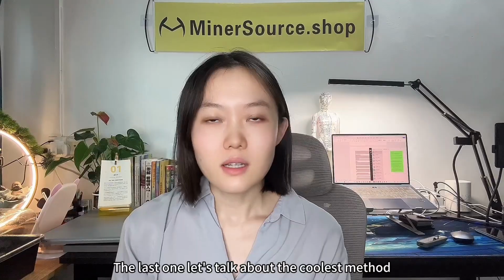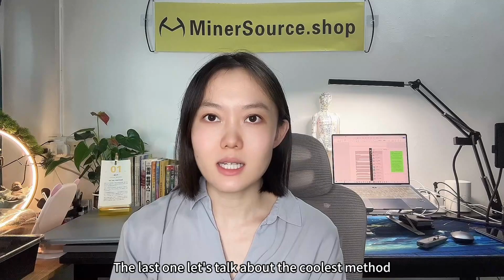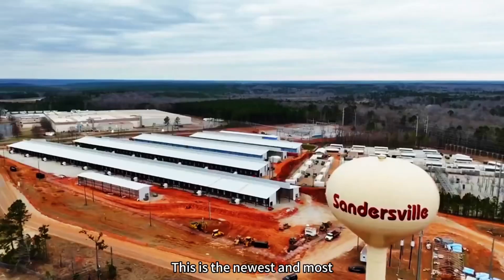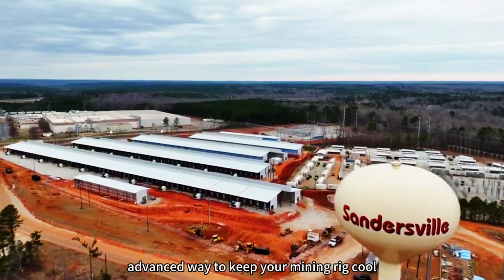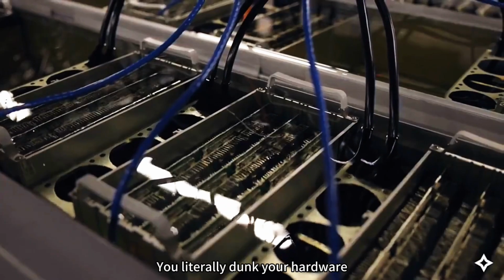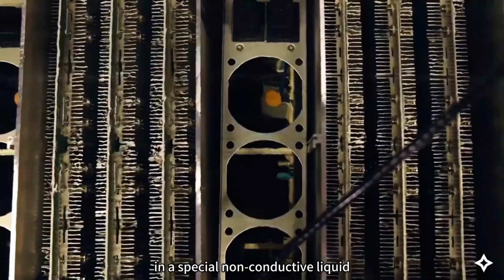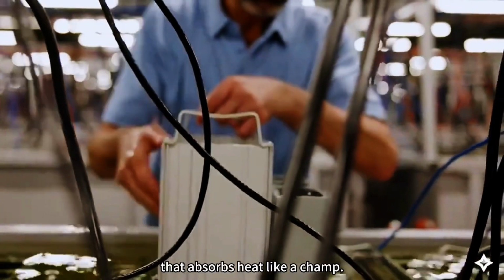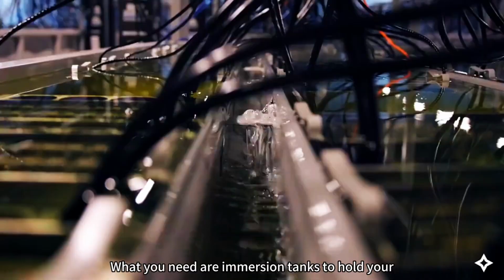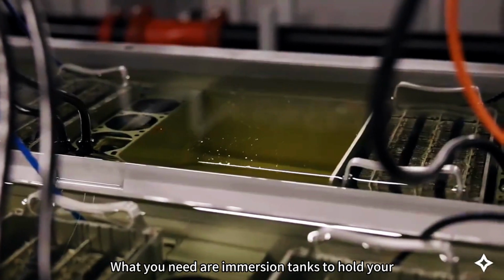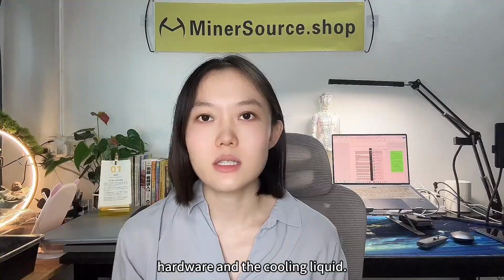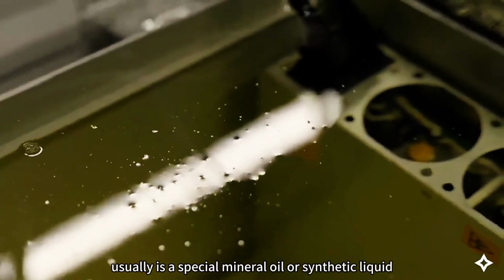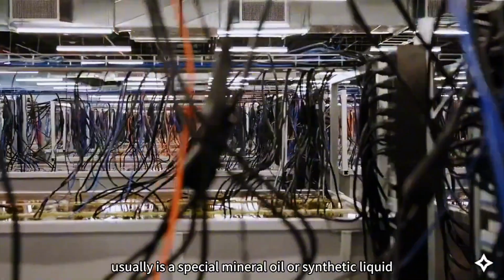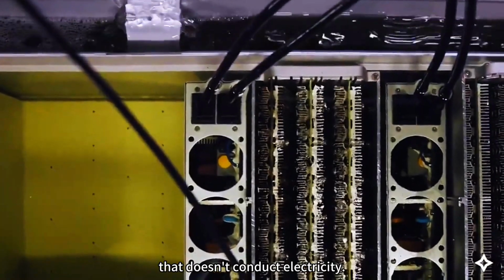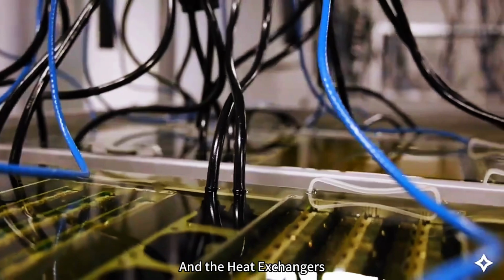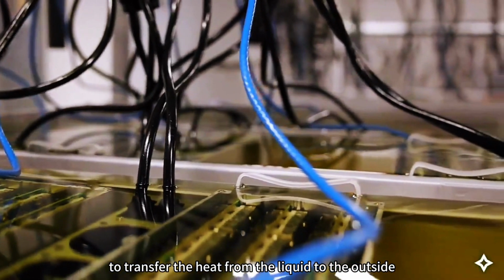The last one is the coolest method: immersion oil cooling. This is the newest and most advanced way to keep your mining rig cool. You literally dunk your hardware in a special non-conductive liquid that absorbs heat like a champ. What you need is immersion tanks to hold your hardware and the cooling liquid, usually a special mineral oil or synthetic liquid that doesn't conduct electricity, plus heat exchangers to transfer heat from the liquid to the outside.